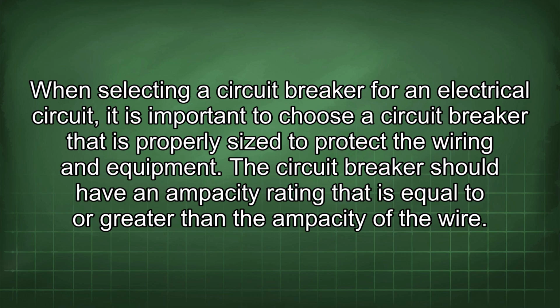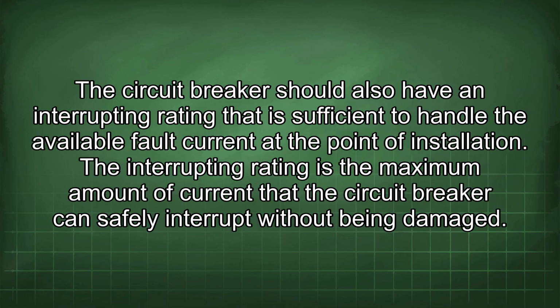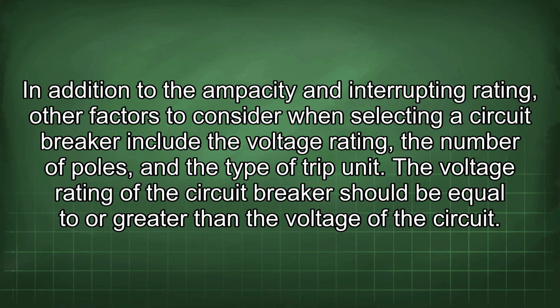The circuit breaker should have an ampacity rating that is equal to or greater than the ampacity of the wire. The circuit breaker should also have an interrupting rating that is sufficient to handle the available fault current at the point of installation. The interrupting rating is the maximum amount of current that the circuit breaker can safely interrupt without being damaged. In addition to the ampacity and interrupting rating, other factors to consider when selecting a circuit breaker include the voltage rating, the number of poles, and the type of trip unit.